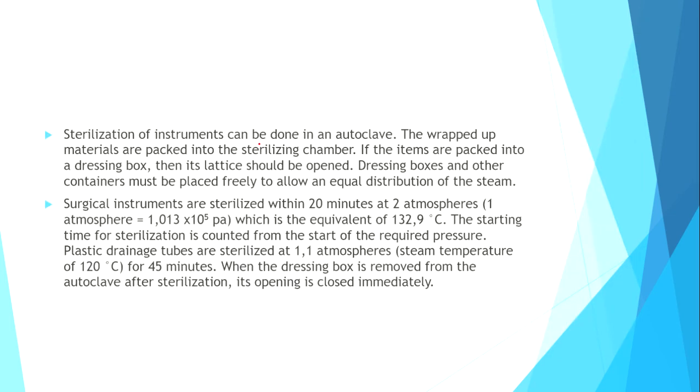Sterilization of instruments can be done in an autoclave. The wrapped materials are packed into the sterilizing chamber. Some are packed into a dressing box, then its lids should be opened. Dressing boxes and other containers must be placed freely to allow an equal distribution of the steam. Surgical instruments are sterilized within 20 minutes at 2 atmospheres.